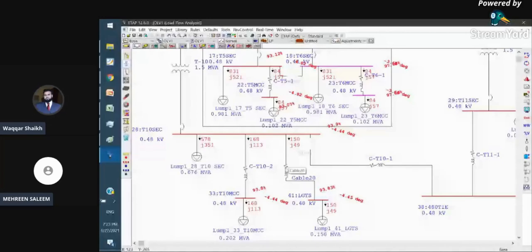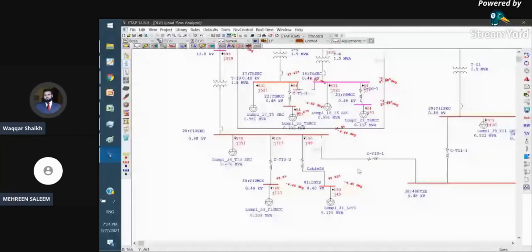So what can be the solutions to overcome this under voltage problem? One solution can be to increase the cable sizes, because by increasing the cable sizes we are decreasing the cable impedance. Resistance is equal to rho L over A, where A is the area of the cross section. When we increase the cable size, it will increase the ampacity of the cable, and by increasing the area we are decreasing the resistance. Less resistance means less voltage drop, so we get a much better voltage profile.